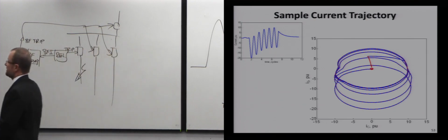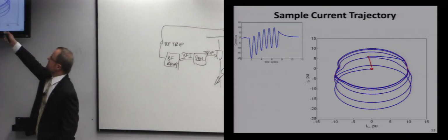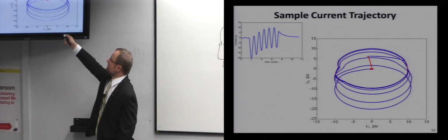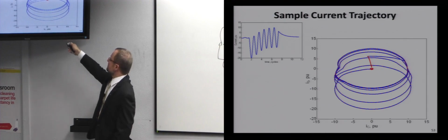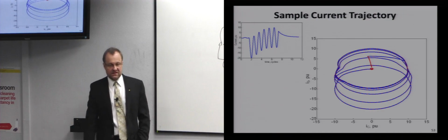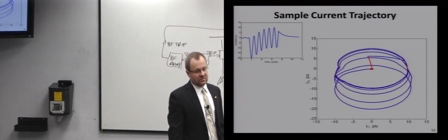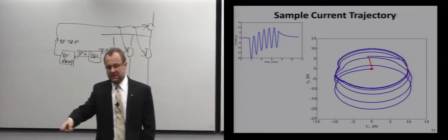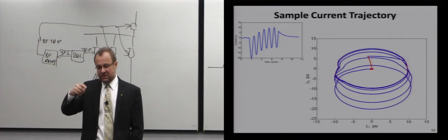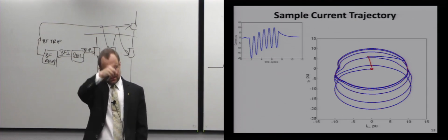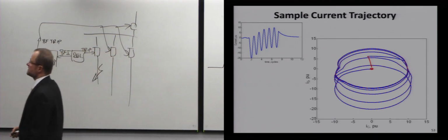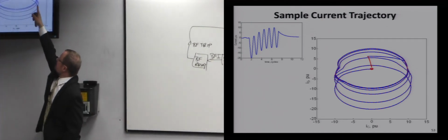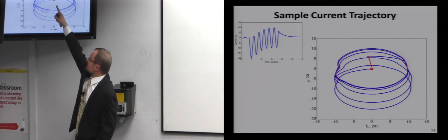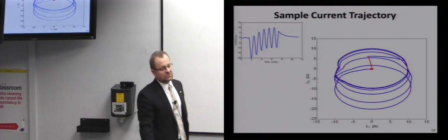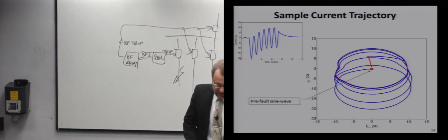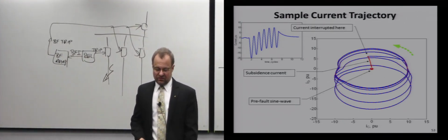When I look at this current through my two components, this is what I will see, and how to interpret that. When I am before the fault, I am making a circle here, a small one, small magnitude, pure AC, right? When the fault happens, this is what I am doing. If this was a steady state perfect sine wave with no exponential DC component, I would be making a perfect circle, right? If I look at the sine wave and plot the sine wave against the derivative of that sine wave, I am making a circle. And then when the current is interrupted, around 7 cycles, my rotating motion stops, and I start resetting towards zero along the line that is shown in red, right? So there is a very distinctive difference between fault and no fault situation.